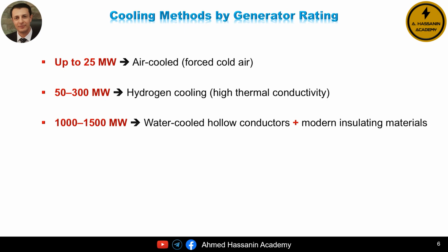Now let's talk about how we cool synchronous generators, because the cooling method really depends on the generator rating. For small to medium units, up to about 25 megawatts, the solution is simple.